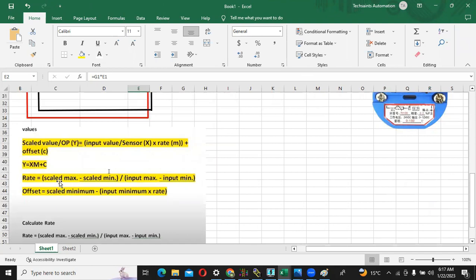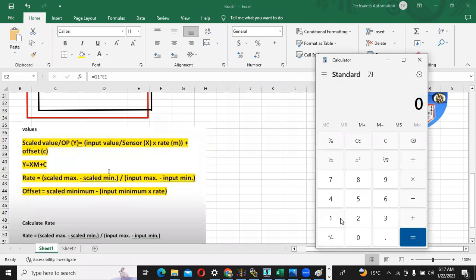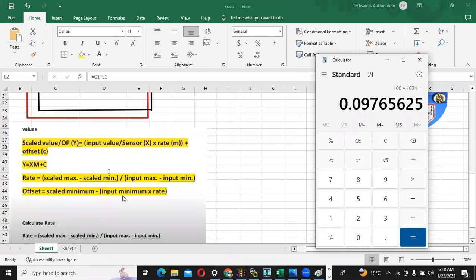When I will do 100 minus 0 is 100, input maximum 1024 minus 0. If I open this calculator, 100 divided by 1024, we are getting this value 0.09765. Now we have offset: scaled minimum is 0 minus input minimum is 0.